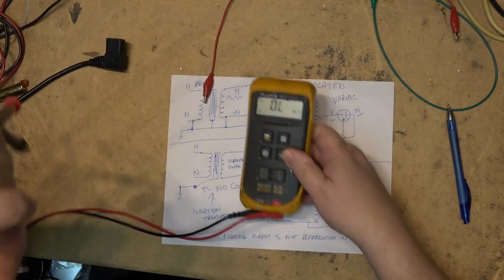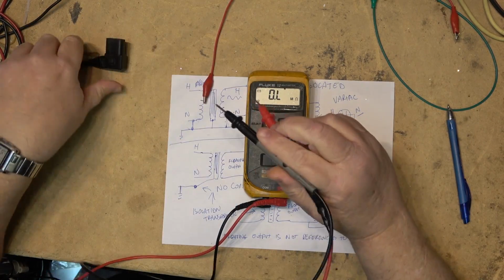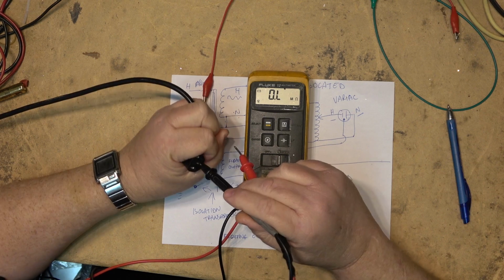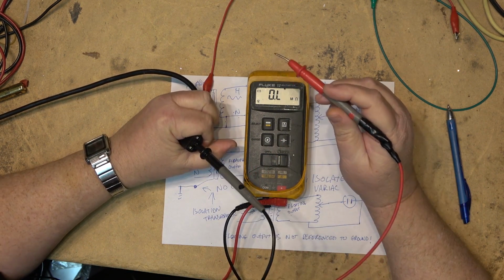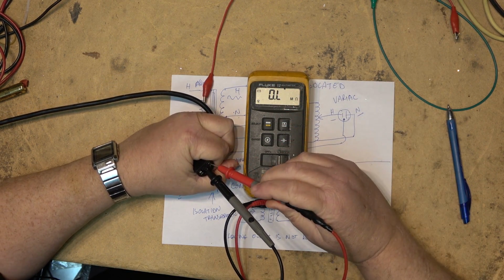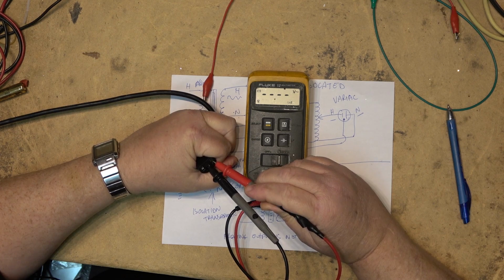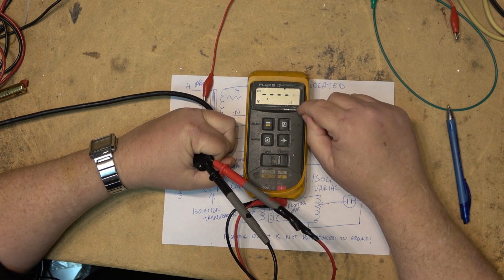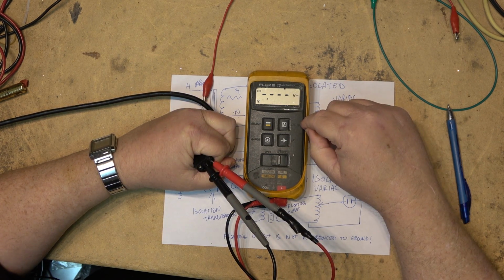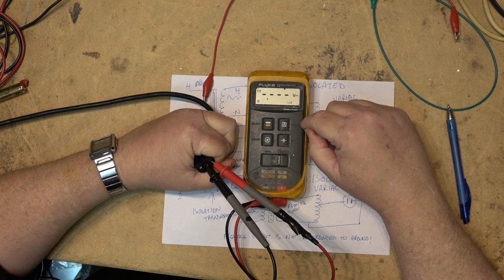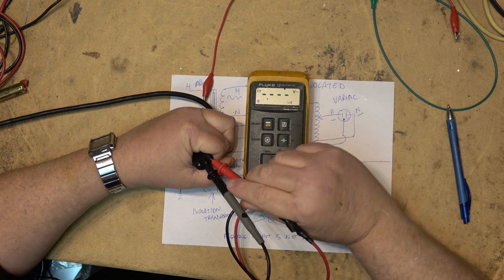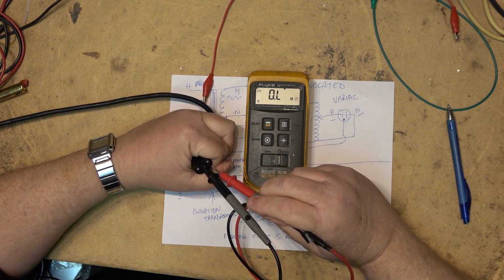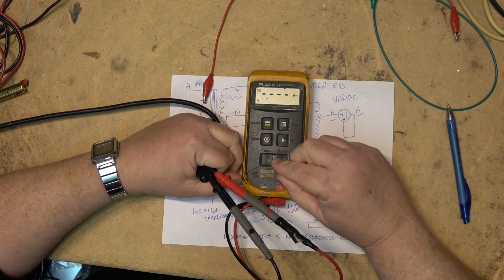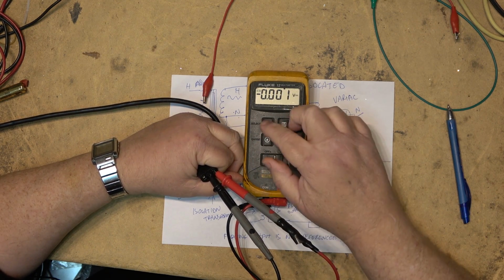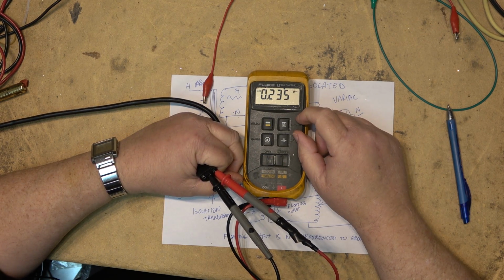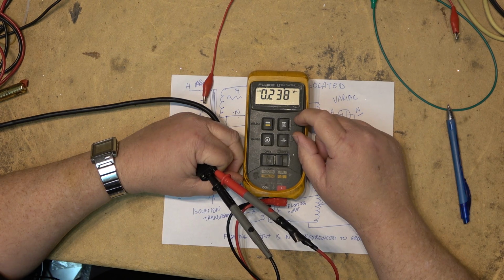If I take my meter and I measure between ground and the neutral, it's measuring that there's a volt or two on here, but normally this would measure 0 ohms. But there's a little bit of rise between the ground and the neutral here. How many volts is it? I get like 0.2 volts, and that's of course affecting the meter.